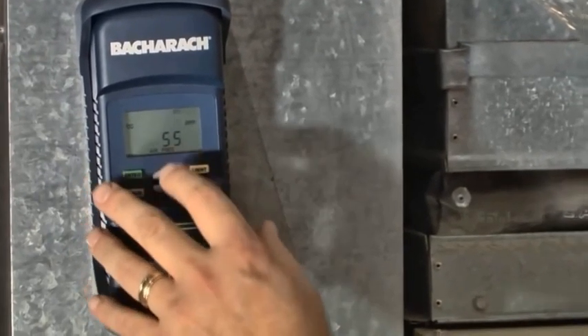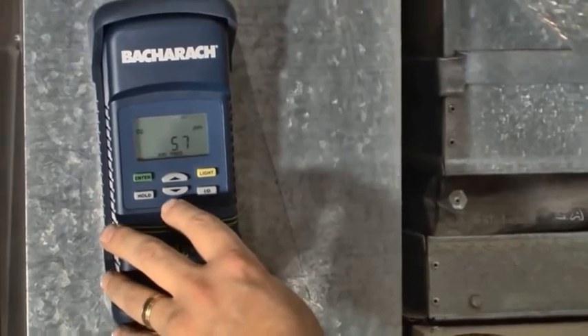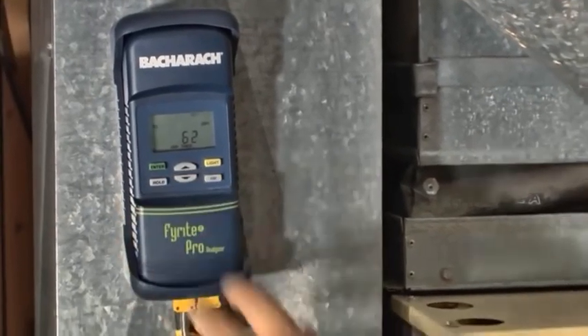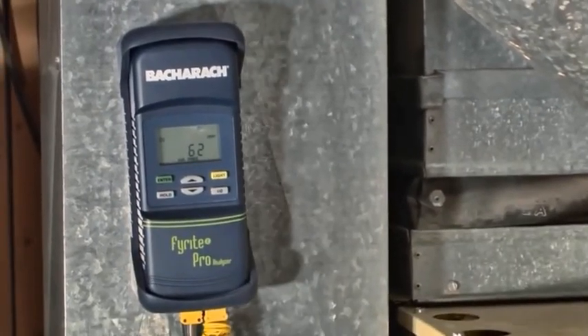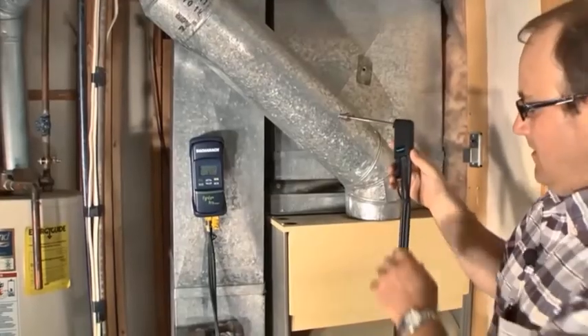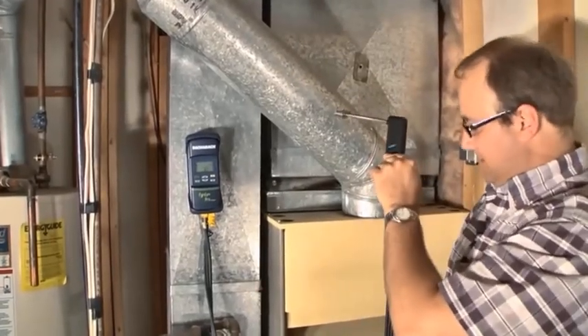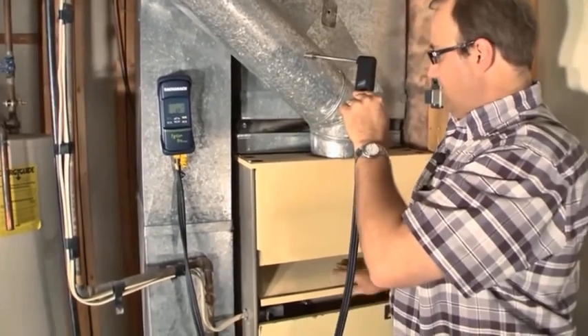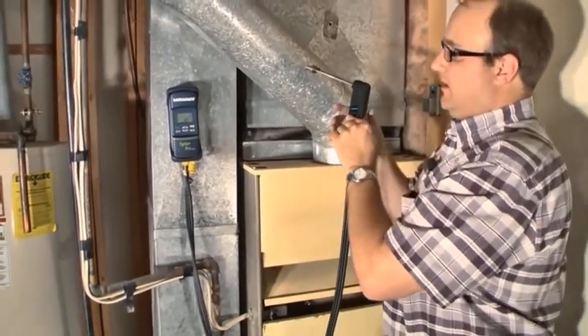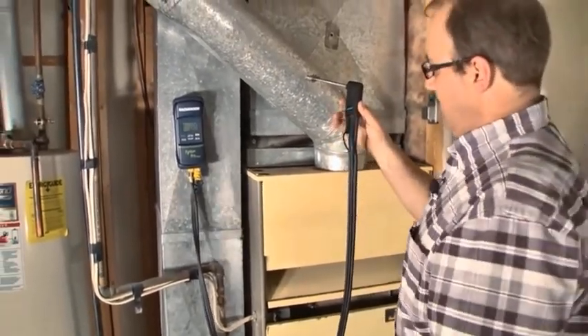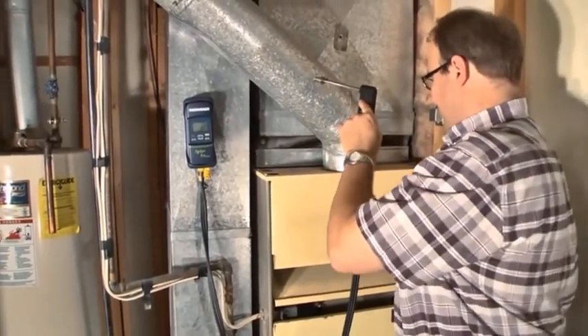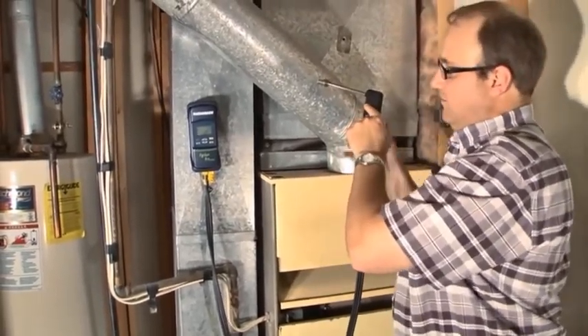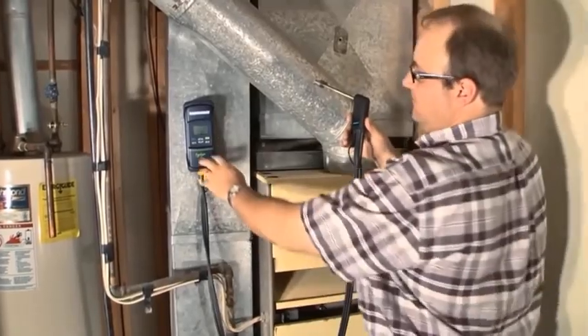Air free is 55 parts per million. It's going up though. We'll just kind of watch it and see. So basically what this is telling me is there's enough air diluting through here to those two burners that were kicking out a lot of parts per million. We have enough oxygen mixing in to dilute the parts per million way down.